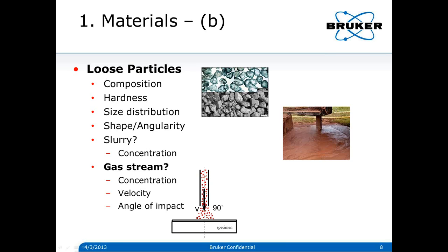If we're making materials to resist erosive wear, not only the concentration and velocity matter, but the angle of impact is really important. At high angles of impact, we would choose a different material — such as a soft or compliant material because it's more of a fatigue and fracture phenomenon — versus a low angle of impact where we want a harder material. So those are the things we consider on the materials side.